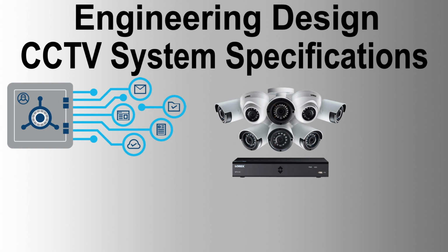Camera video transmission. Compression techniques. MPEG-4 compression techniques shall be utilized for compressing video image data at the encoder from 1 Mbps to 4 Mbps or better for transmission. Frames per second. All cameras shall be capable of sending full frame rate 25 frames per second, FPS, images for security and surveillance applications. Operators shall be able to configure to low frames per second around 1 to 3 FPS under normal conditions. In the event of an alarm, the recorded frame rate speed can be automatically increased to a full frame rate of 25 FPS.